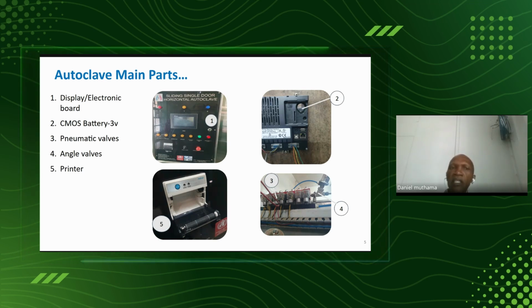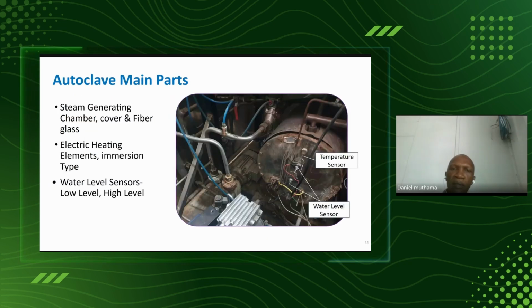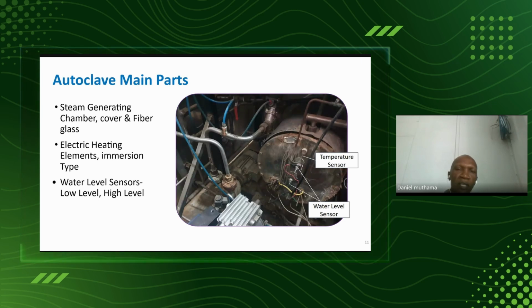So after every 6 months, the engineer is supposed to clean the generating chamber. In case, as the engineer had said, the immersion type element is faulty. Can we go to the generating chamber down? These two are the set of electric heating elements. This one and this one is a set of electric heating elements. This is one set. This one set contains 3 elements. There is this one. This will go inside, then make a U. This is one set. This is another set. Then this is the third set, this one here. In case one of these electric heating elements is faulty and these two are working okay, then you will find that the heating time takes longer.